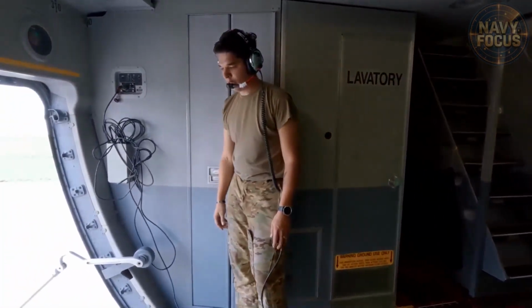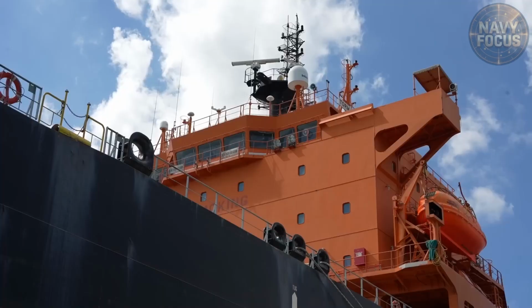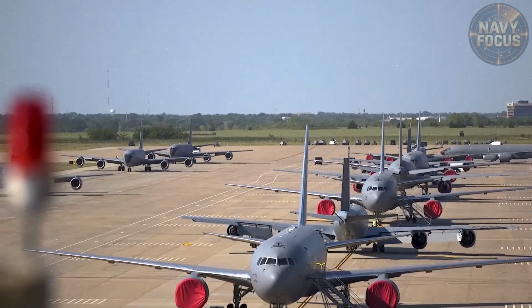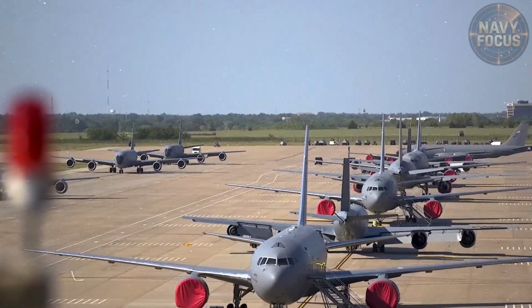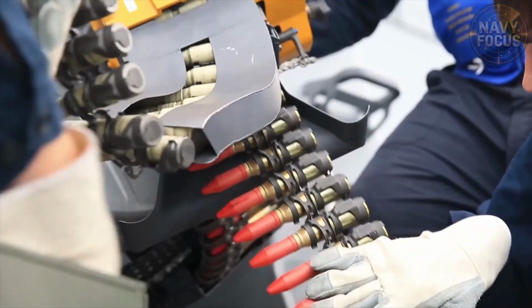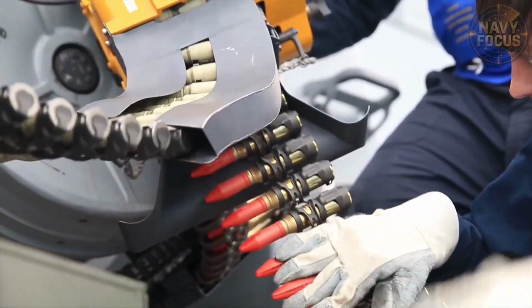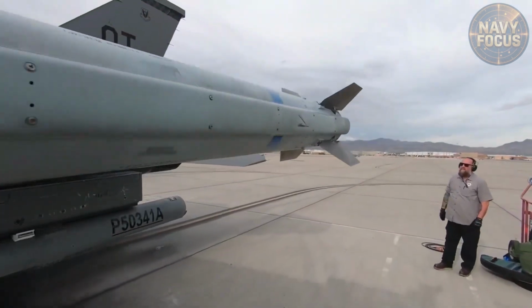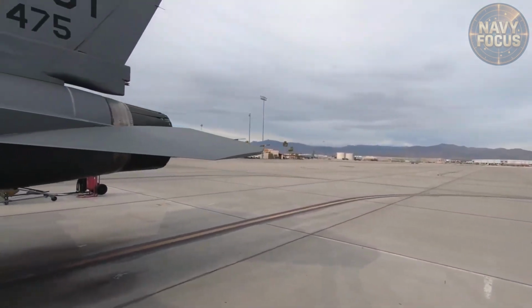The rate of hydraulic fluid spraying from the rupture drops immediately. The fire does not go out. The residual hydraulic fluid that has already escaped from the ruptured line and soaked into the utility space surfaces is still burning, but the continuous fuel supply is gone. The fire is now running on residual fuel rather than a pressurized spray.